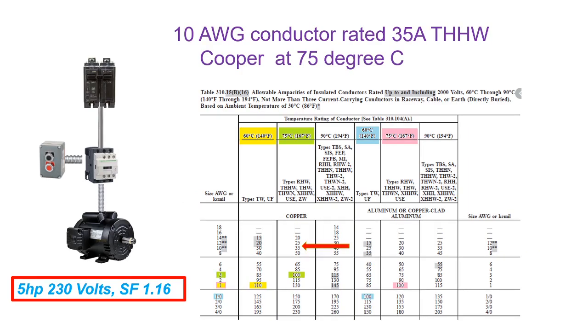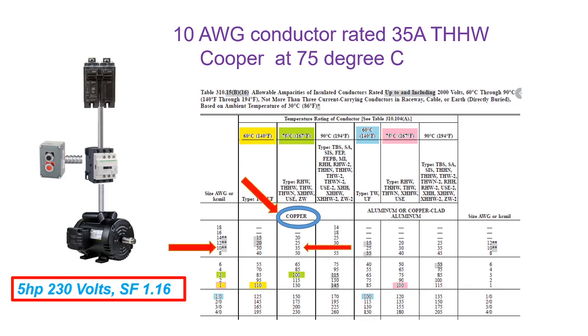Step 3: find the conductor using Table 310.15(B)(16). For 35 amperes with a copper conductor, remember that the default motor terminal rating is 75 degrees C as per NEC Table 110.14(C). The conductor selected is 10 AWG.